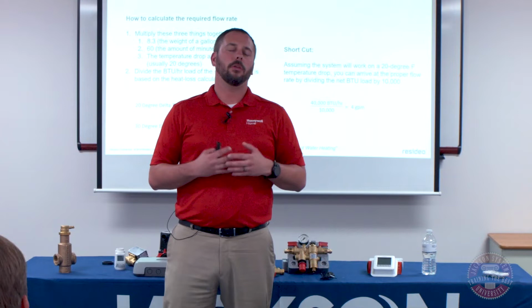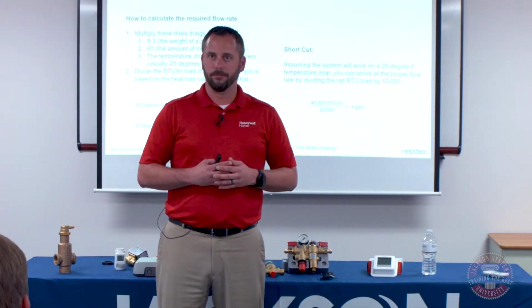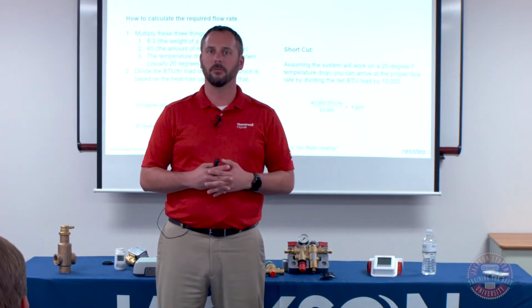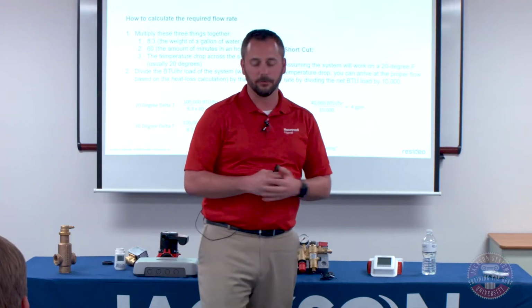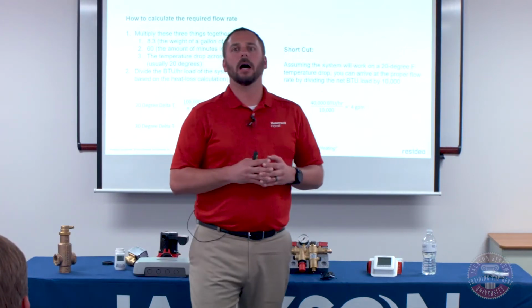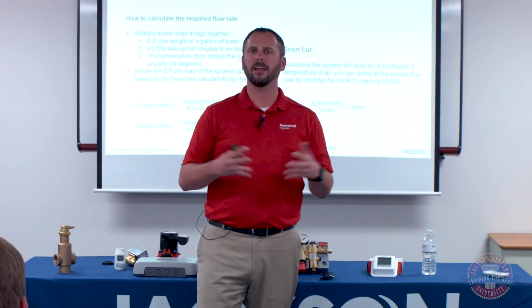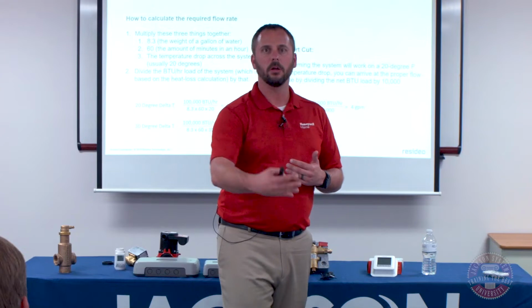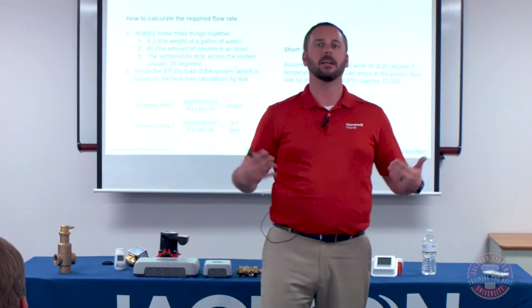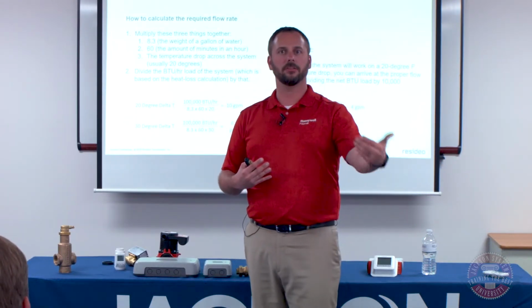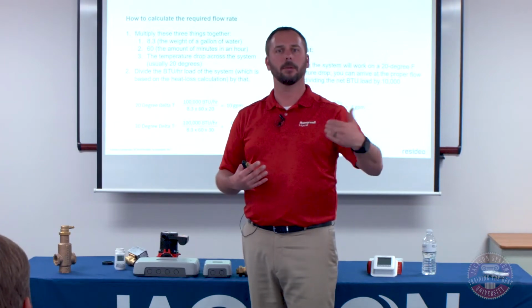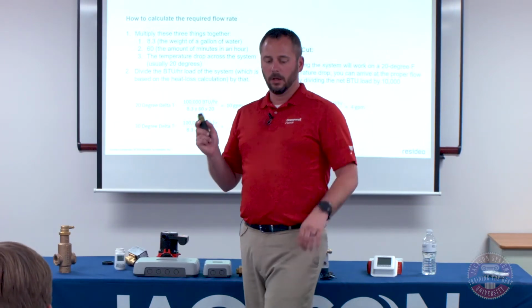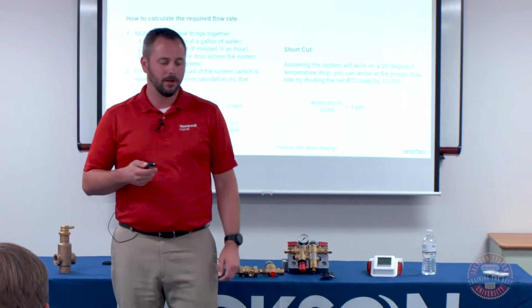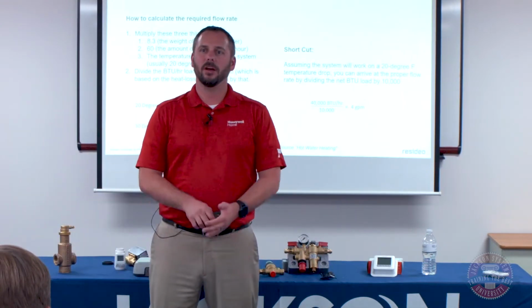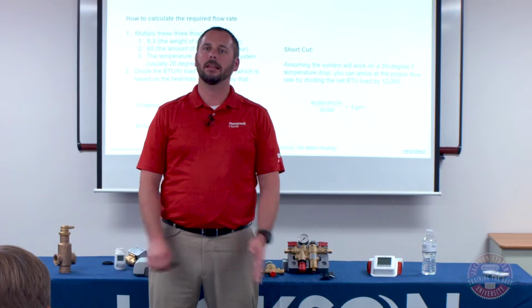If I change that to a 30-degree temperature differential, which I was mentioning I like to do on my system designs when I was doing in-floor heating systems, you're multiplying it by a bigger number down at the bottom, which brings your flow rate slower. So it makes sense, right? You move the water slower, it's going to have a bigger temperature change by the time it gets back to us. So if it leaves at 130, it's coming back at 100 versus leaving at 130 and coming back at 110. But that can mean you can use a much smaller pump. The shortcut, if you're doing some stuff quick, just take the output and divide by 10,000.